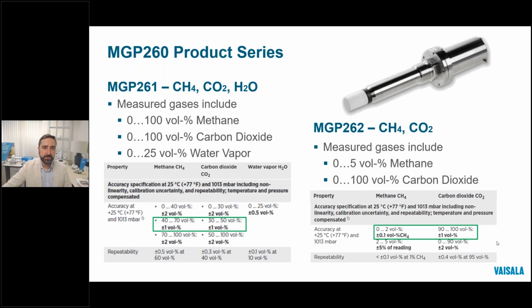Now, the MGP 262 model was designed for tail gas measurement, providing full range CO2 and a highly accurate low-level methane measurement with a 0.1% accuracy for 2% and below of methane. The default scale is 0 to 5% for methane, but that scale can be expanded either at our factory or in the field, and it will still provide a high accuracy of plus or minus 5% of the reading and not the full scale. And now some of you may be wondering about H2S or oxygen measurement, but we don't offer those products at this time. But while we don't sell anything for them ourselves, we can help with some recommendations. Next, please.